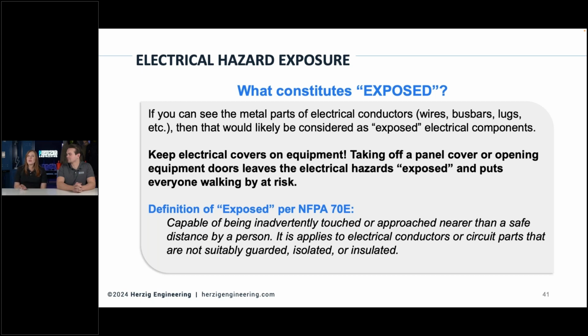It could be beneficial to limit access to breakers, for example, as long as everybody who needs to be able to turn equipment on and off has the keys to unlock it. Who has access to the distribution board? Do you have non-qualified workers around the area where, if they decided to, they could open it? That's something to consider. And if they could, maybe consider having it locked so only qualified personnel have access to it. It's the best practice.